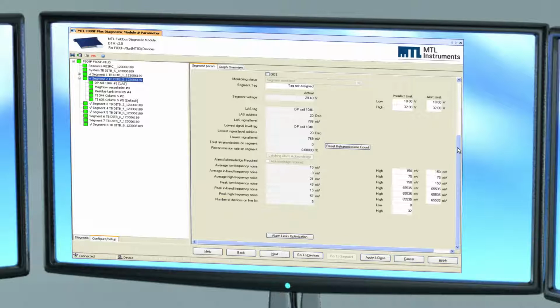Scrolling down the segment view reveals the measured average and peak noise in each of 3 frequency bands. Note that in the Configure/Setup view, the pre-alert and alert limits for each measured parameter are also displayed. During setup, the limits can be automatically set to default values by clicking the Alarm Limits Optimization button. This significantly reduces the setup time by applying predefined limits based on the Fieldbus power supply type and measured actual values. All the alert and pre-alert levels may, however, be manually amended to suit the project requirements.